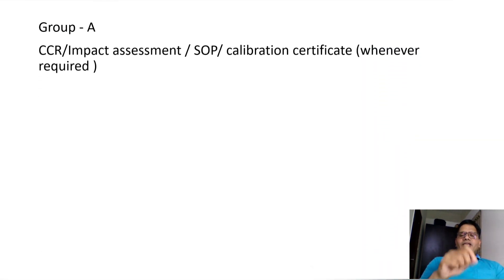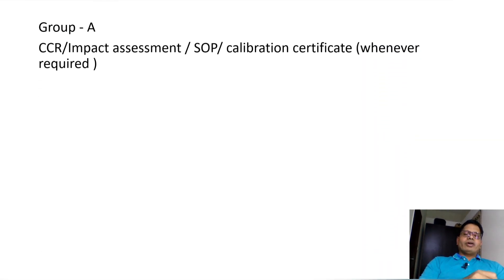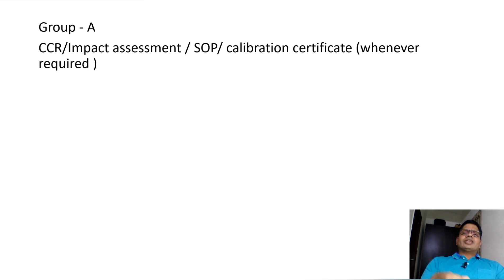Based on the impact assessment, you decide whether the instrument falls in Group A, Group B, or Group C category. For Group A, the required qualification documents are: change control, impact assessment to identify the group, a standard operating procedure, and if calibration is required, attach the calibration certificate. That is all the qualification required for a Group A instrument.